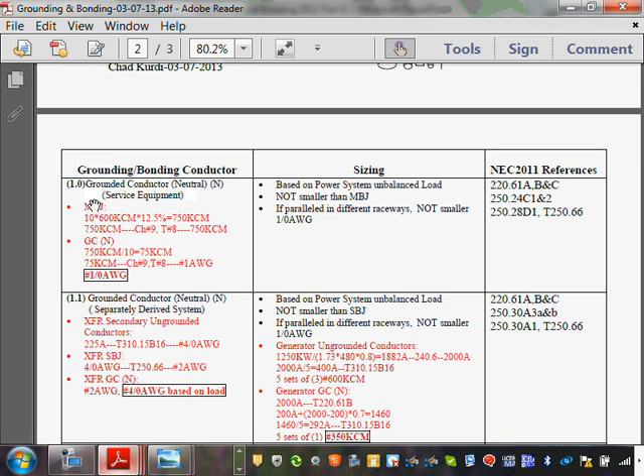To size the neutral, it can't be less than the main bonding jumper. So what you do is you take the 10, that's from the code, you multiply it because 10 sets multiplied by the largest size of each set, 600. Then you take 12.5%. I hope you guys are familiar with these numbers. You take the 12.5%, will give you 750 kcm. So then from 750 kcm, you go to chapter 9, table 8, will give you 750 kcm. That's your main bonding jumper.